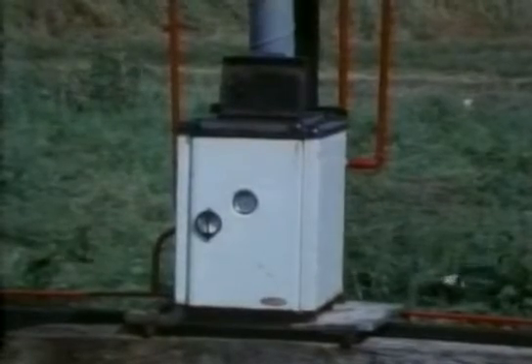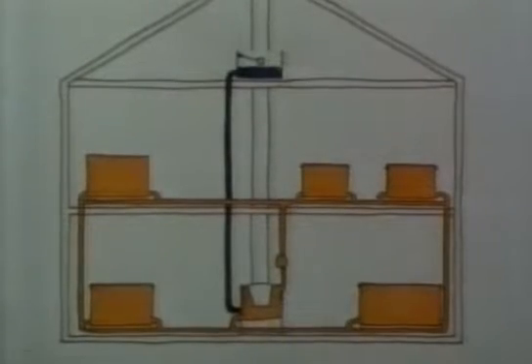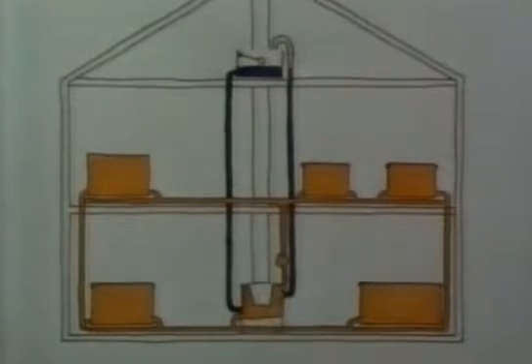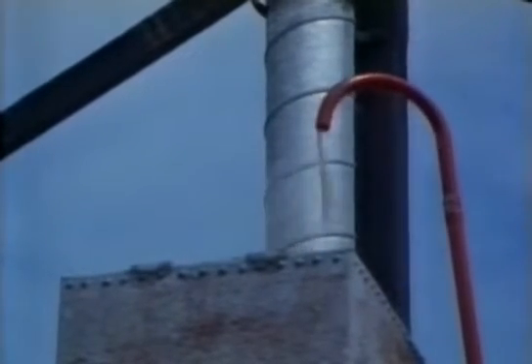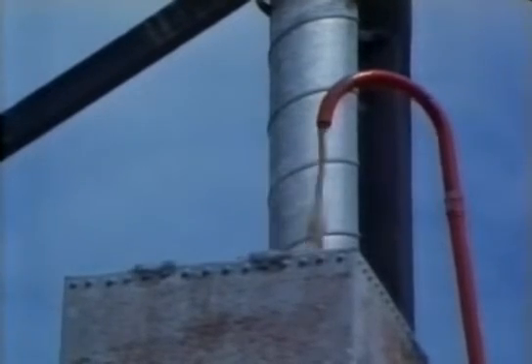The pipes round the boiler do look a bit complicated. There's one pipe to a tank in the roof to fill the system with water. There's also a vent pipe which lets the water inside expand as it heats up and lets water and steam out in case it boils. Here we've deliberately overheated this system and the steam harmlessly comes out of the vent, while fresh water comes in through the feed pipe to stop the boiler boiling dry.